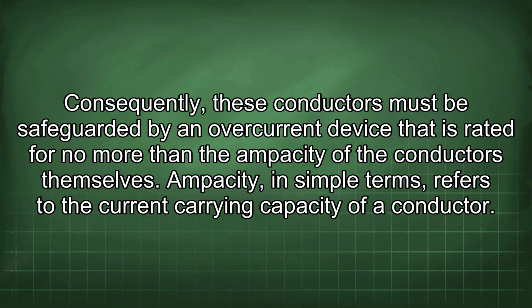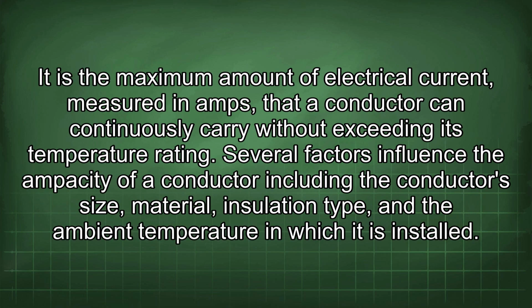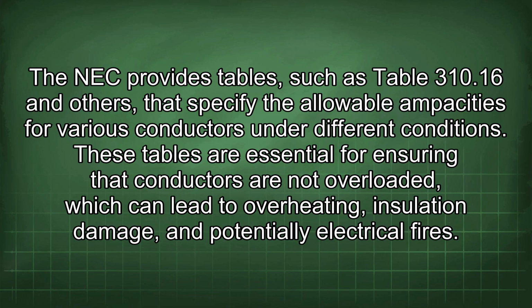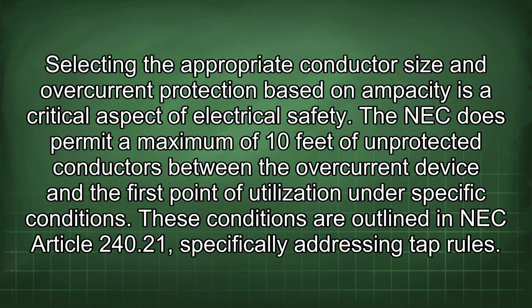Ampacity, in simple terms, refers to the current carrying capacity of a conductor. It is the maximum amount of electrical current, measured in amps, that a conductor can continuously carry without exceeding its temperature rating. Several factors influence the ampacity of a conductor, including the conductor's size, material, insulation type, and the ambient temperature in which it is installed. The NEC provides tables such as Table 310.16 and others that specify the allowable ampacities for various conductors under different conditions. These tables are essential for ensuring that conductors are not overloaded, which can lead to overheating, insulation damage, and potentially electrical fires.